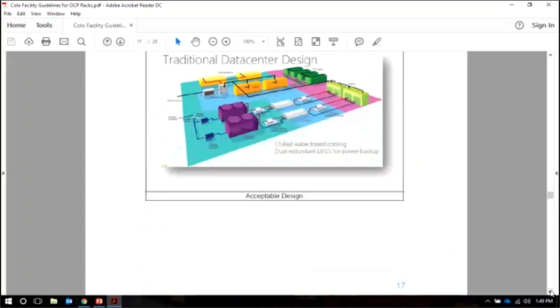The biggest change in facility power distribution design is the ability to bring non-UPS protected power right to the rack, if the rack has a battery backup unit. The key there is the generator startup time within the spec of the holdup time for the BBU. Pretty easy to figure out, but that's an interesting way colocation facilities could differentiate themselves, by having that option.